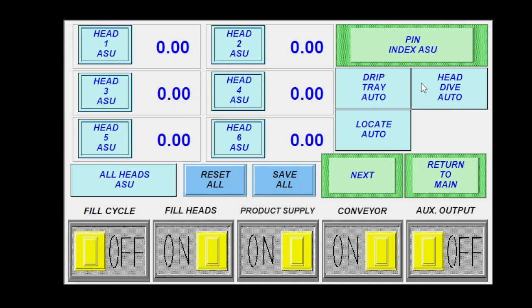You can toggle your drip tray, your head dive, your locate, everything right here. But let's say I wanted to do head number one. In a real basic circumstance, I would just click head one ASU, reset ASU. So this should be zeros. And then I'm going to have a container under fill head one and I'm going to push and hold this button.